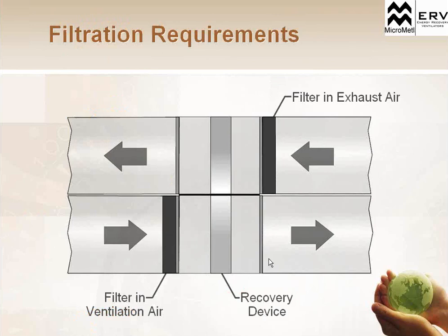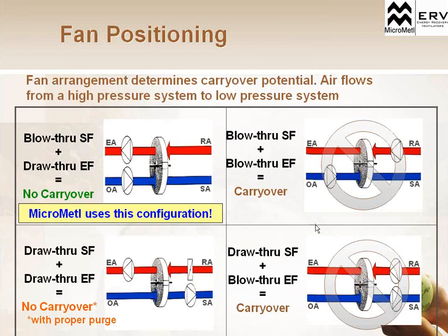When we do that, there are filtration requirements. When we're bringing in the outside ventilation air and we're exhausting air from the building, we want to pre-filter those two air streams to make sure nothing gets on the wheel. That filtration is just meant to protect the wheel. That is not for indoor air quality. That should all be handled by your heating and ventilation piece of equipment, your rooftop or air handler. These filters on the system are actually protecting the wheel, making sure those polymer fibers aren't clogged with any gunk, leaves, or anything like that. So that filter is just to protect the wheel itself. The wheel blower arrangement, how we're pulling air across that wheel that's sitting between the two airflows, is actually very critical as well.